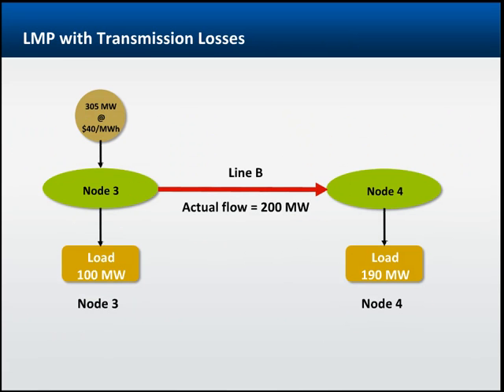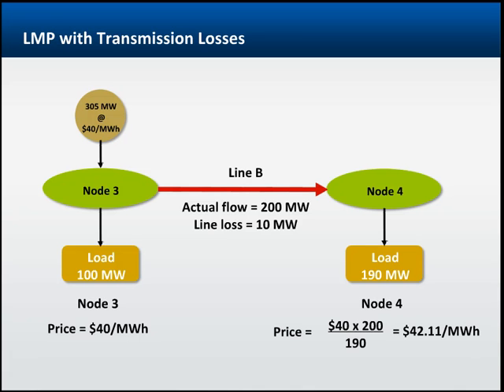In previous examples, line losses were not included in the LMP calculation. Some ISOs use this method, while others include the cost of line losses. If there are line losses on the transmission line between two nodes, and the ISO procedure calls for line losses to be included in the LMP calculation, prices can then be different in two adjacent nodes even if there is no transmission congestion, since line losses raise the price at the node where the power flows in. In this example, the price at node 3 is $40, while the price at node 4 is $42.11, since we are adding in the cost of line losses for getting power to node 4.